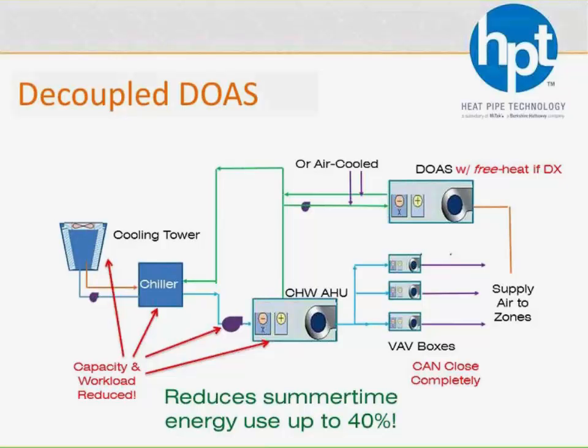And I do want to point out that that supply air, or the air coming out of the DOAS unit, and right there it is showing it being delivered out into the zone. But it could be done many ways. It could go directly to the space. It could go back into the inlet of the air handler like was shown before, except now it's been pre-treated. It could be fed to the mechanical room as a plenum and then drawn from by each air handler as needed. A lot of times you see decoupled systems serving primary air to chilled beams as well. So there's a lot of uses and a lot of ways, like any system, that a dedicated outside air system can be designed.